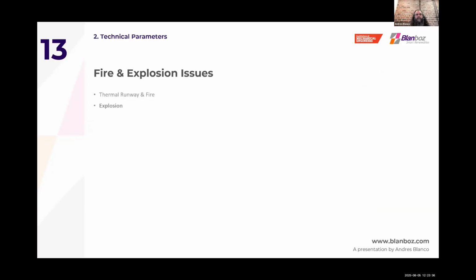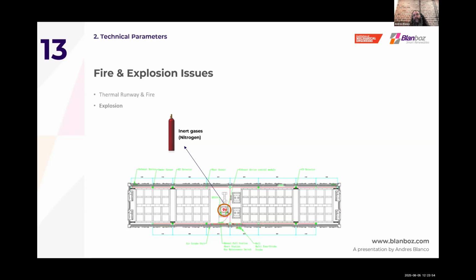Explosion, very important. Sometimes it's forgotten around the issues with fire, and it's only fire that takes all of the attention. For me, it's very critical. We have been involved in different projects that have had issues with explosion. The risk is obviously slightly lower than the risk of fire, but because now we have gas fire suppression being used in battery containers, it increases the likelihood of explosion.